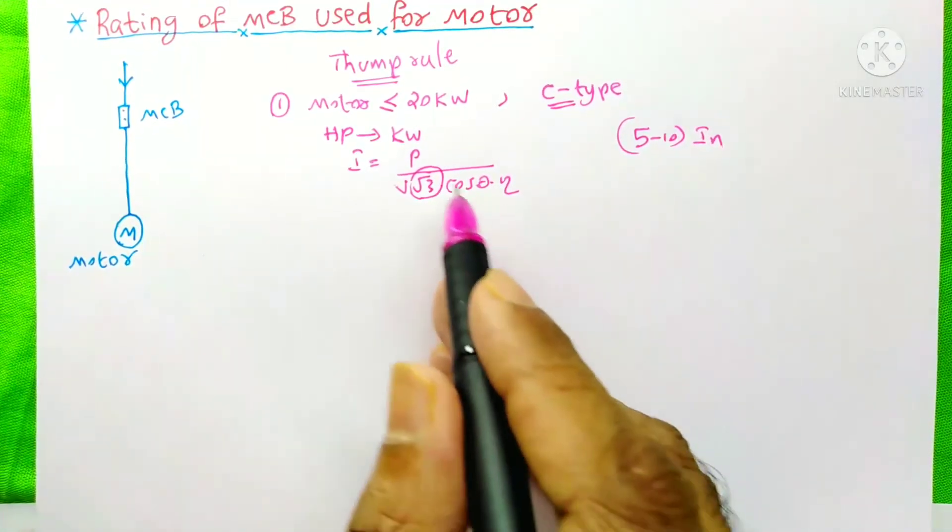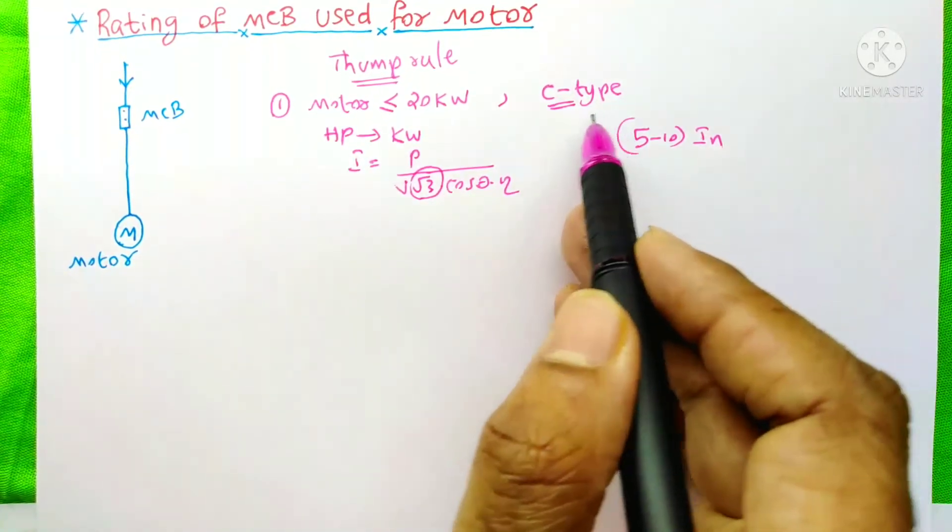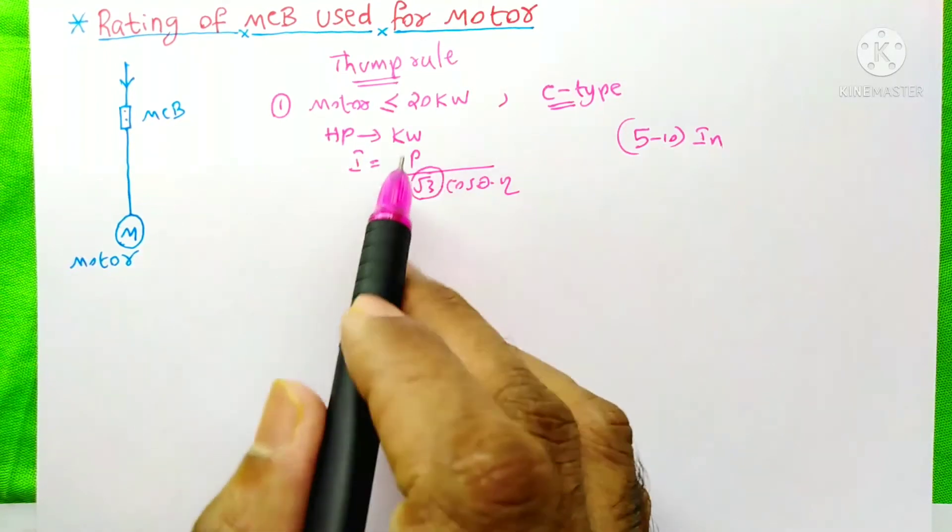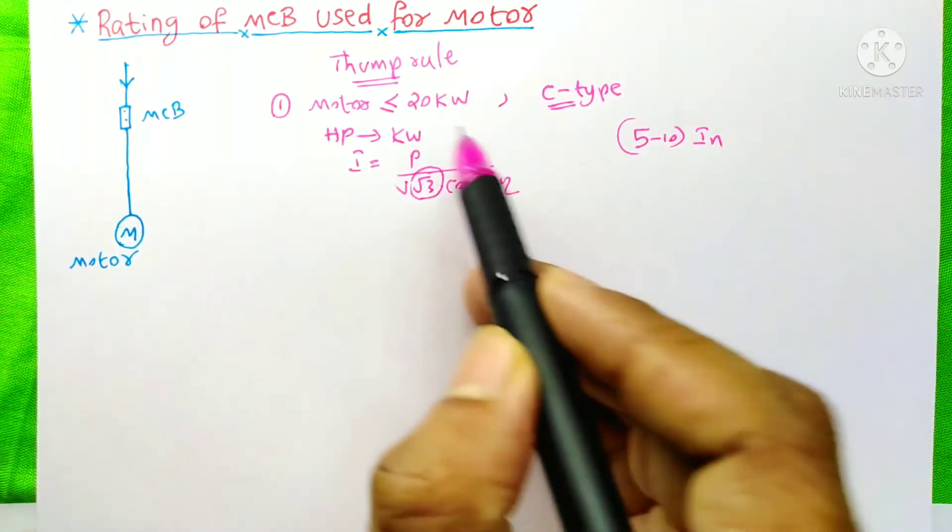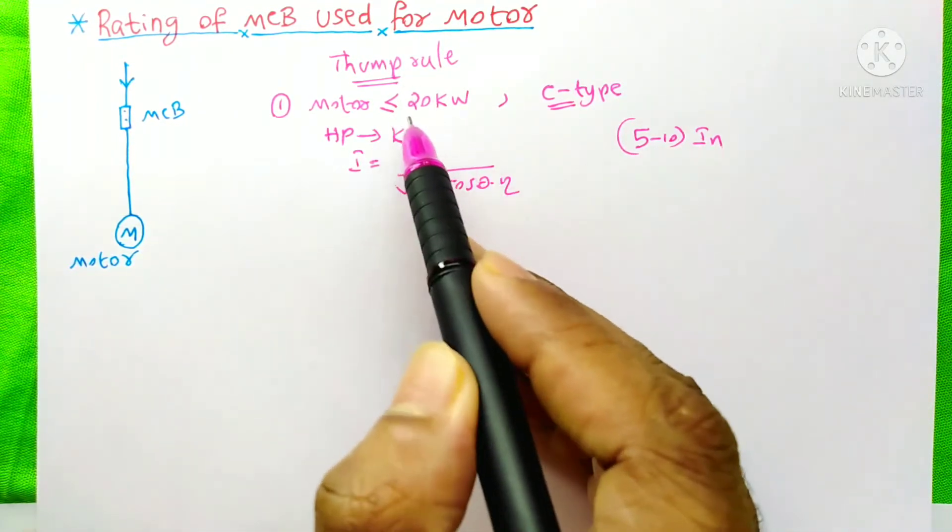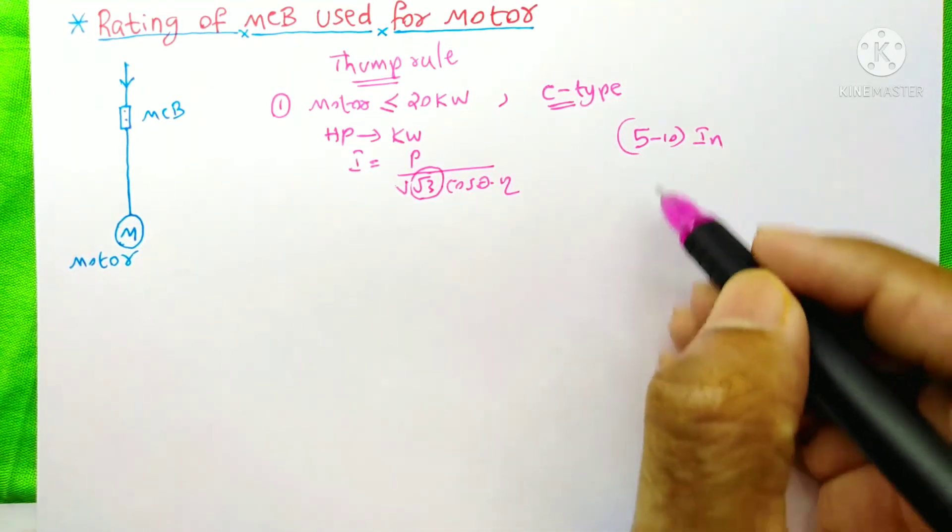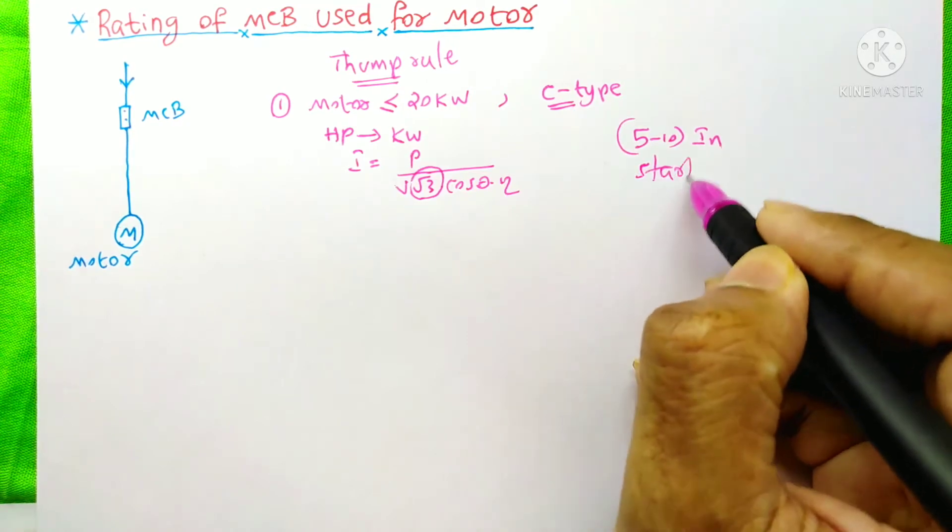Do you know why the engineers always choose the C-type MCB for the motors less than or equal to 20kW? Because they know very well that the motor in this capacity will take only 5 to 10 times of the rated current during the starting of the motor.